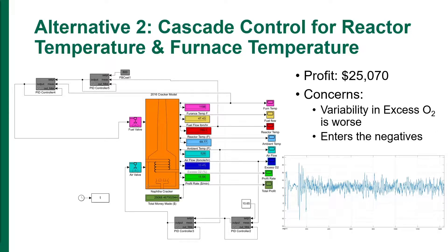The inner loop controller, PID controller 4, controlled the furnace temperature, while the outer loop controller, PID controller 5, controlled the reactor temperature.